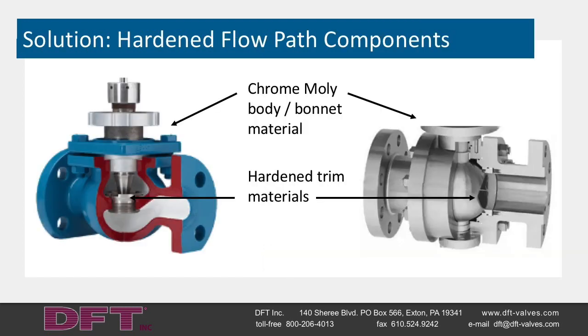Solution: hardened flow path components. Globe-style, ball-style, and Venturi-style control valves are all present in slurry applications. All three styles use hardened materials such as chromoly, stellite, or ceramic trim configurations to combat the erosive effect of slurries. Globe-style and ball-style control valves also use hardened body and bonnet materials such as chromoly to reduce the effects of slurry on the valve body. Using hardened body and bonnet materials can be very expensive. These hardened materials will extend the useful life of the valve, but eventually the body will wear out and have to be replaced.